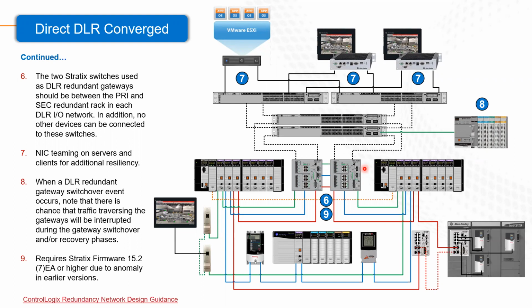Quick thing just to add, so just so you guys are aware, redundancy for the L8 controllers as of version 33 only supports 1 controller per chassis. So what Mike is showing, you essentially have 1 single controller with multiple Ethernet adapters. Every color that he showed is a different DLR.